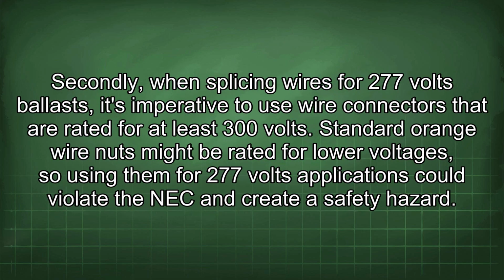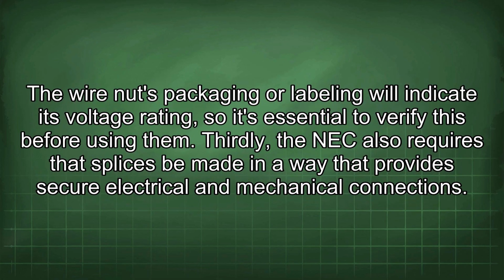Secondly, when splicing wires for 277 volts ballast, it's imperative to use wire connectors that are rated for at least 300 volts. Standard orange wire nuts might be rated for lower voltages, so using them for 277 volts applications could violate the NEC and create a safety hazard. The wire nuts packaging or labeling will indicate its voltage rating, so it's essential to verify this before using them.